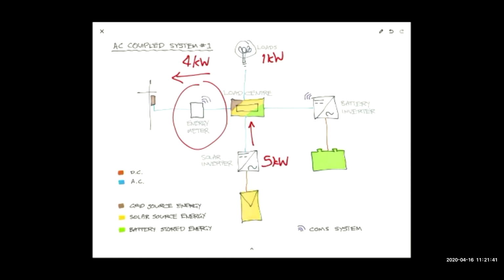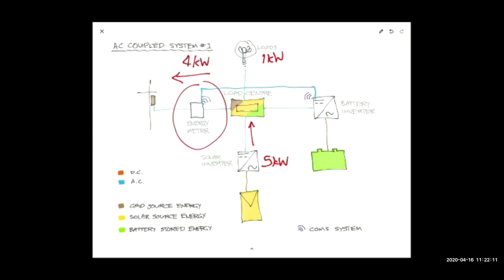You want to turn that around and store it in your battery. But how does the battery inverter know when to charge? It needs that energy meter to communicate the energy flow, usually via a comms cable, but it can be wireless. The comms cable tells the battery inverter there's an opportunity to capture spilled renewable energy - that's the terminology we use, spilling energy. So it tries to turn that around, stopping it flowing the wrong way, sending 1 kilowatt to the loads and 4 kilowatts to the battery. The energy meter then measures zero kilowatts of exchange at the point of connection to the grid.